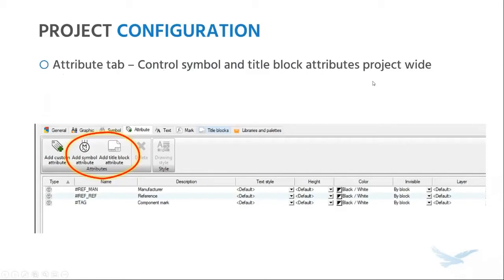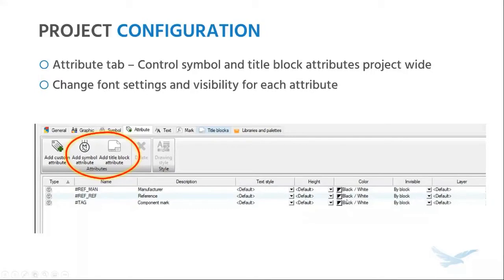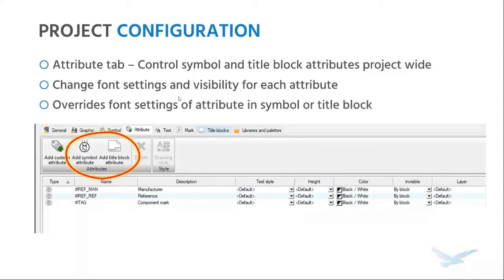Another tab recently added is the attribute tab, which controls symbol and title block attributes across the project. All symbols come with component tags and manufacturer information, but these attributes are not very standardized. The attribute tab allows you to standardize the font and the height of those attributes across the project. You can also control their visibility — for example, if you're generating a customer-facing drawing package, you can choose to make all the manufacturer part numbers invisible before you print it and then show them again for internal purposes. Whatever settings you opt for, these are going to override the font settings in the symbol or title blocks themselves.